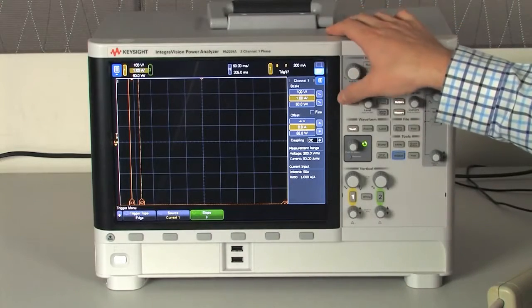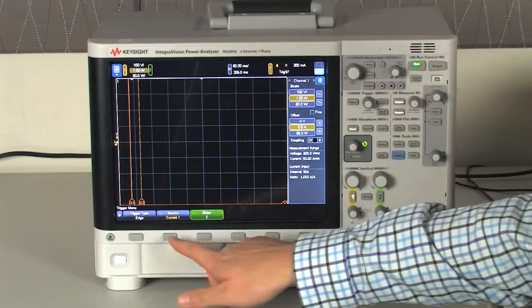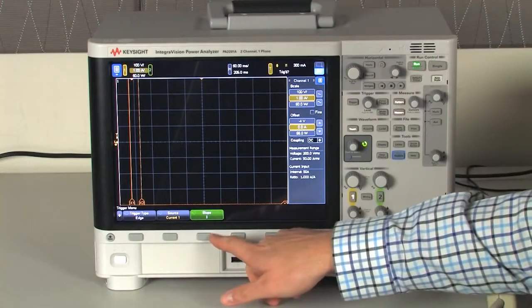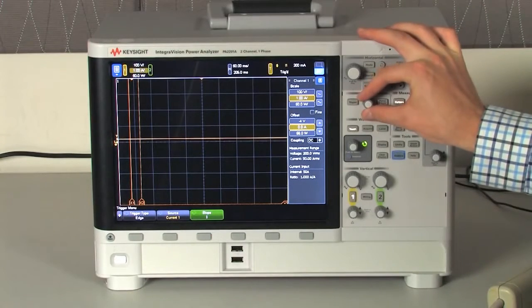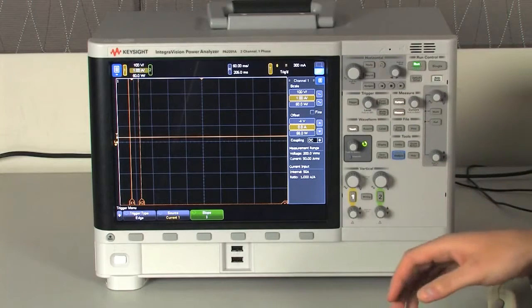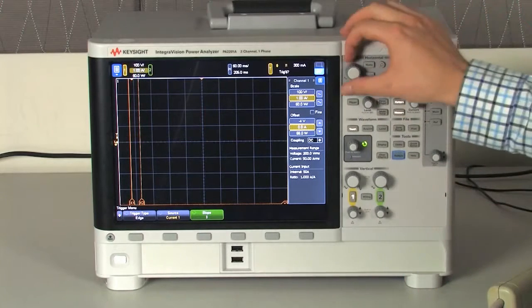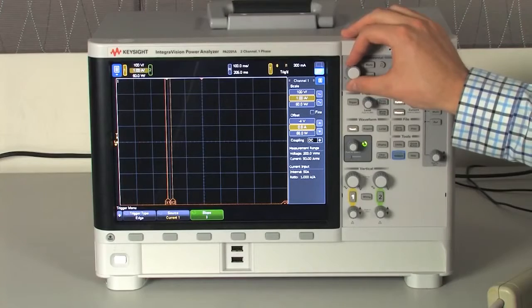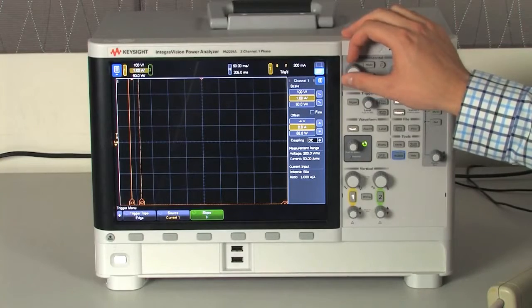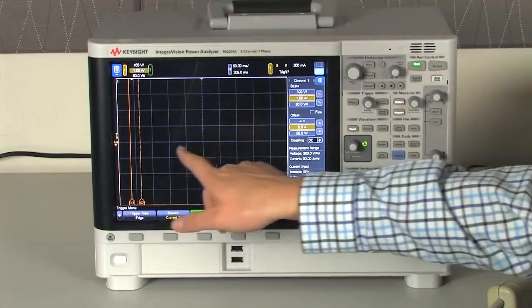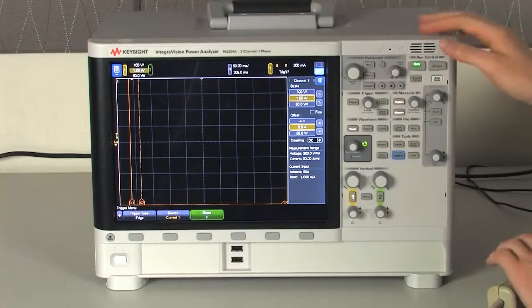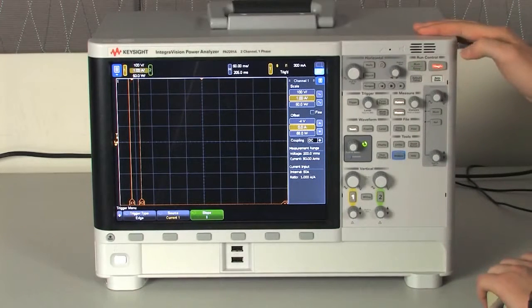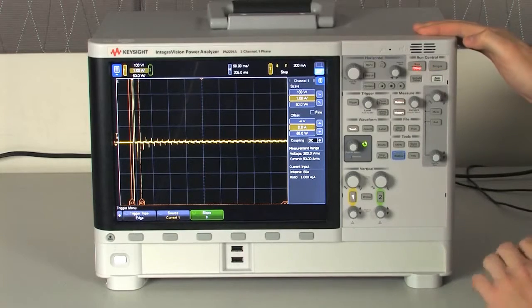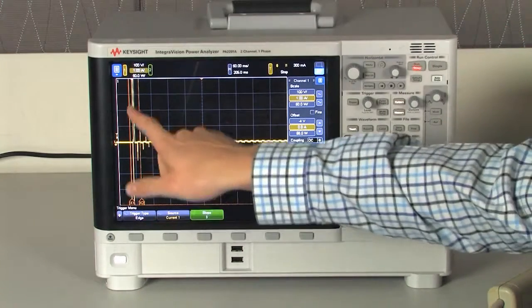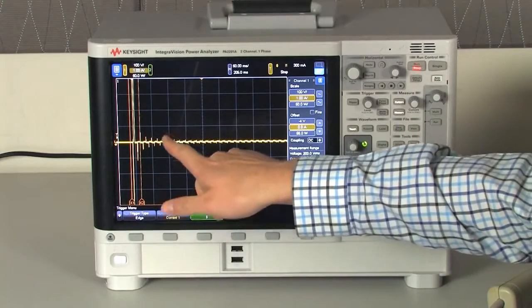The next thing is I want to change the trigger to be triggering on current 1. I'm just going to change the slope to any and set the trigger level to a level that will appropriately trigger for this application. The other thing is I adjusted the horizontal scale to be a little bit larger so I can easily capture the inrush current plus the steady state. So now I'm going to start single shot mode and see if we can capture it. There we go.